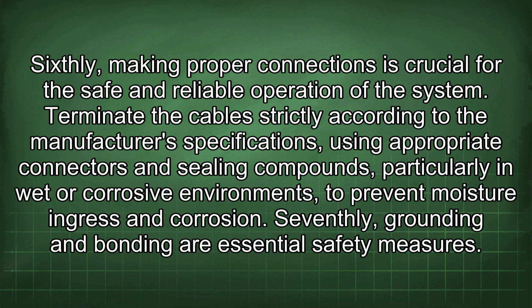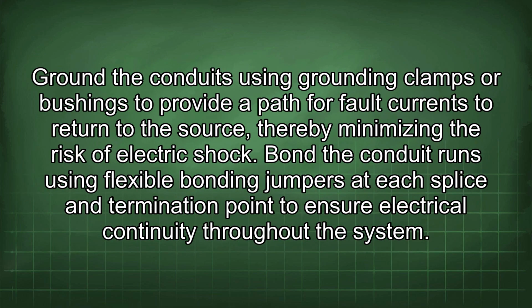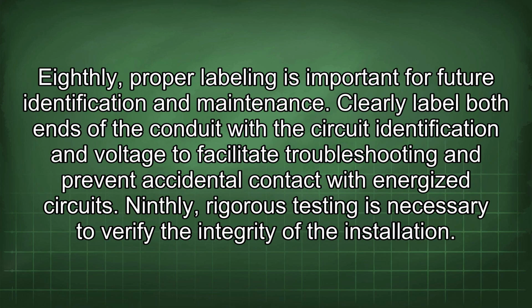Seventhly, grounding and bonding are essential safety measures. Ground the conduits using grounding clamps or bushings to provide a path for fault currents to return to the source, thereby minimizing the risk of electric shock. Bond the conduit runs using flexible bonding jumpers at each splice and termination point to ensure electrical continuity throughout the system.